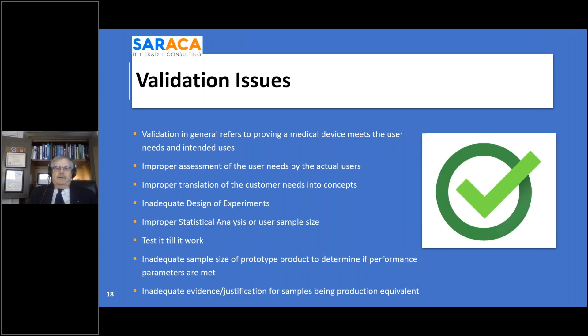That all shows that the proper use, the design of the intended life was not adequate, and it has to be. Another issue is inadequate sample size of prototype product to determine if performance parameters are met. FDA doesn't say that you have to use finished devices, but what they do say is the FDA expects you to use production equivalent. It can't be made by engineers who know what they're doing and make modifications. It has to be done by the people who you expect to make those devices and the processes used to make them.